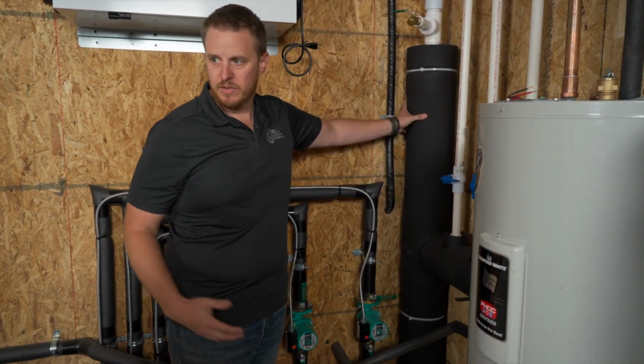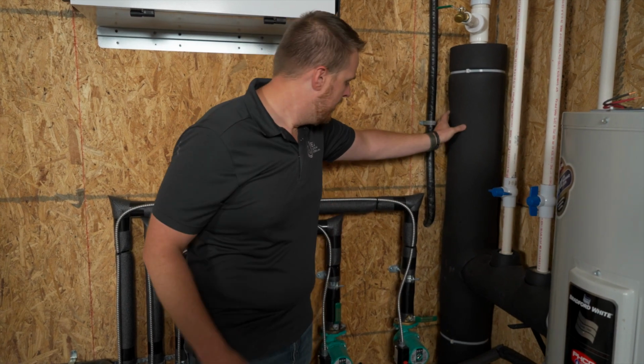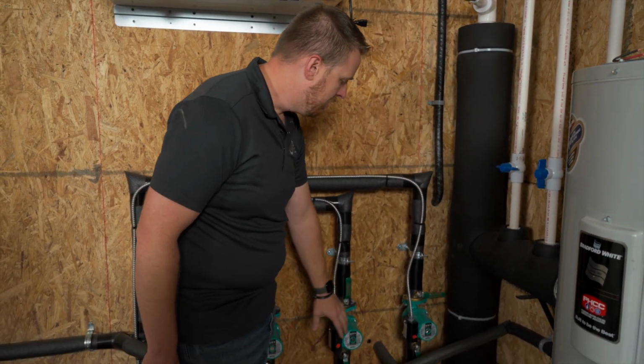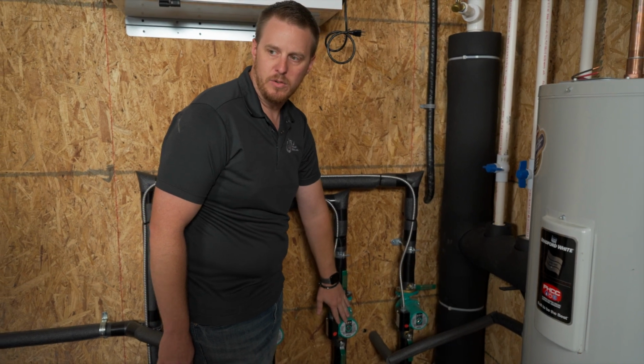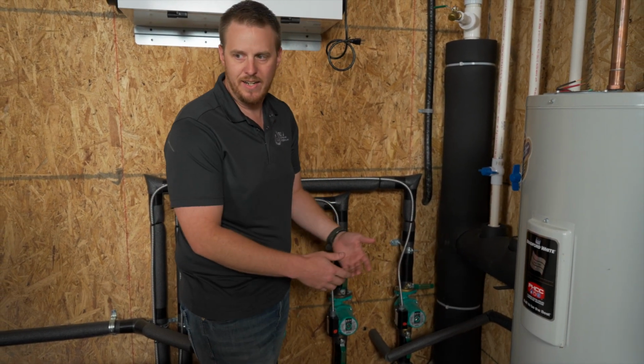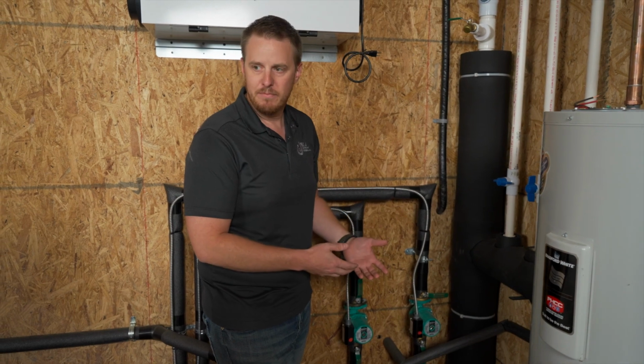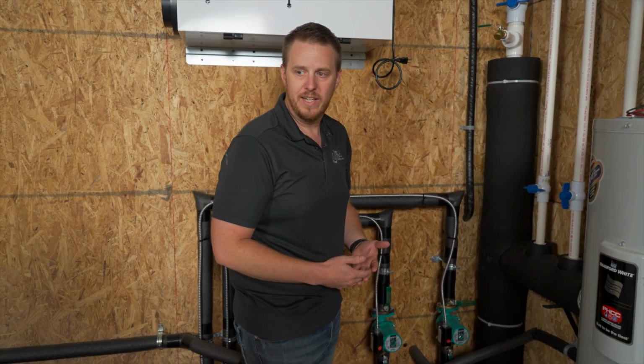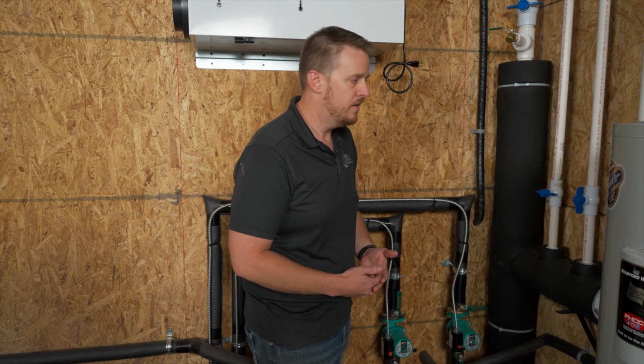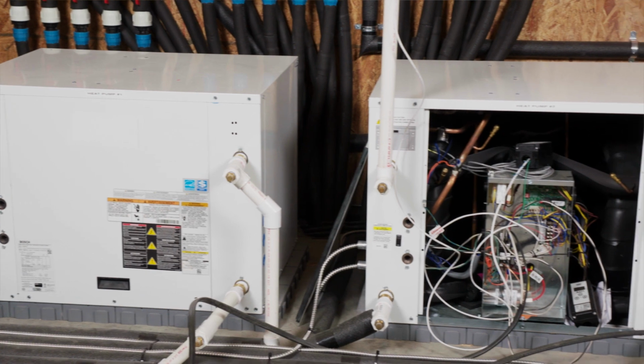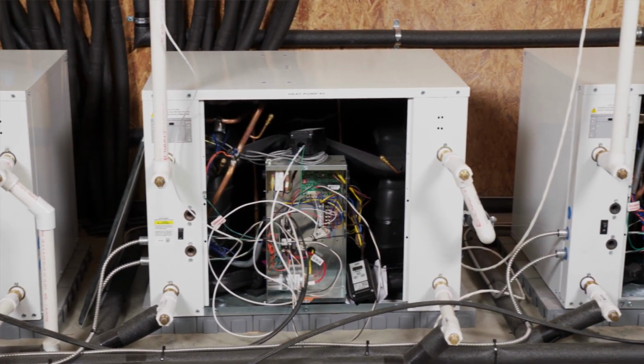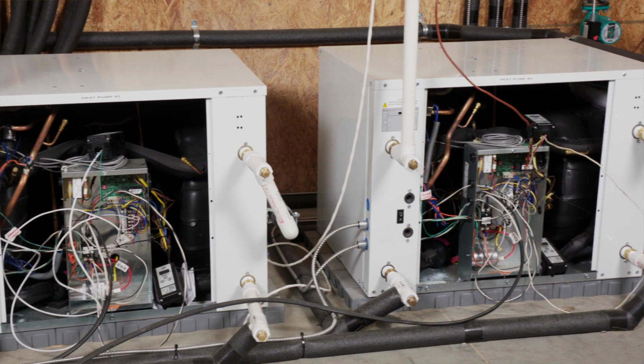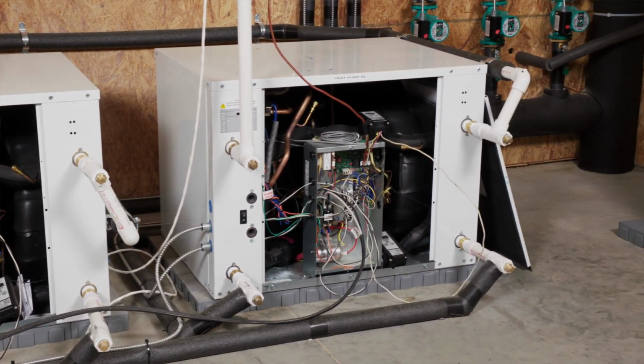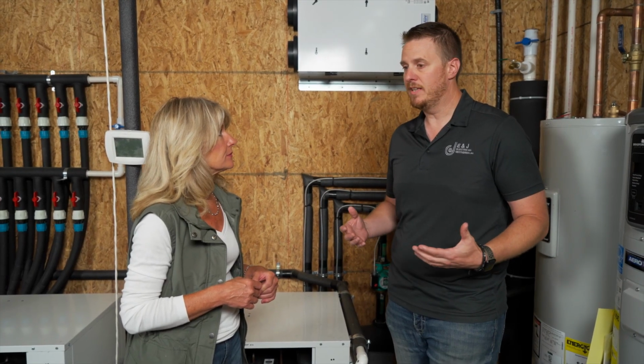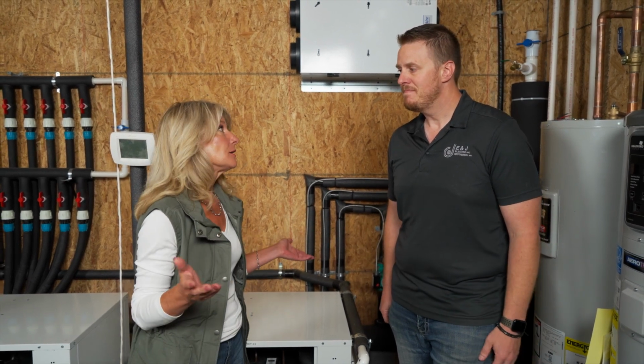So we built a standpipe for the same reason. It acts like the buffer tank. Coming off there, we've got our load side pumps. This is what's actually moving the hot or chilled water to its designated area, whether that's feeding an in-floor heat manifold or running to a chilled water air handler for the cooling portion of the project. Now you have 3 units here. Is that typical? It depends on the size of the house. Remember I said how we do that load calculation to determine what unit. This particular house, we ended up having to go to several units to make sure they had enough heat and cooling to meet that demand. Okay, so it varies depending on the circumstance.